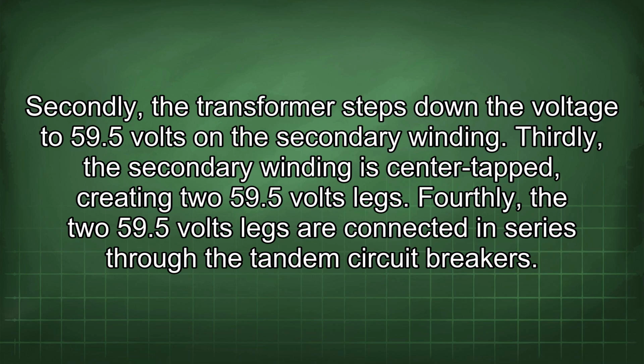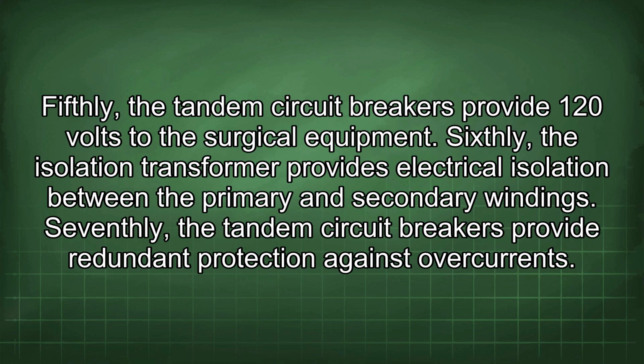Thirdly, the secondary winding is center tapped, creating two 59.5 volts legs. Fourthly, the two 59.5 volts legs are connected in series through the tandem circuit breakers. Fifthly, the tandem circuit breakers provide 120 volts to the surgical equipment. Sixthly, the isolation transformer provides electrical isolation between the primary and secondary windings. Seventhly, the tandem circuit breakers provide redundant protection against overcurrents.